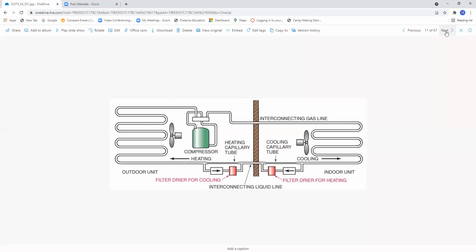Okay, in this diagram here, which I think is found on page 1285 of your textbook, this is figure 43.21, placing a liquid line filter dryer in the heat pump refrigerant piping. So basically, here's your filter dryers for the cooling side and for the heating side. And remember, typically on most heat pump installations, split systems I'm talking about now, they're typically going to install a biflow version of this liquid line filter dryer.